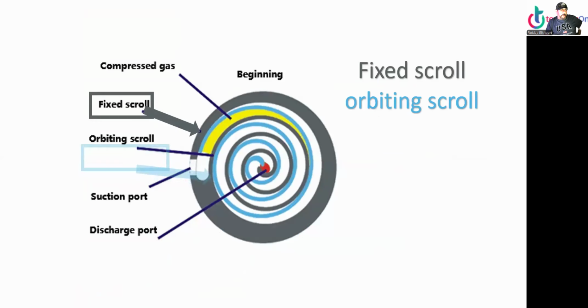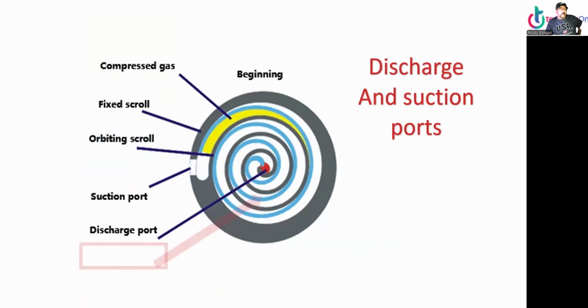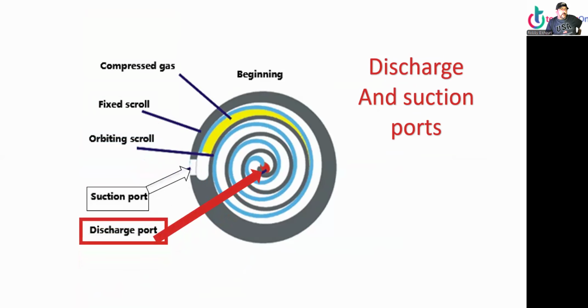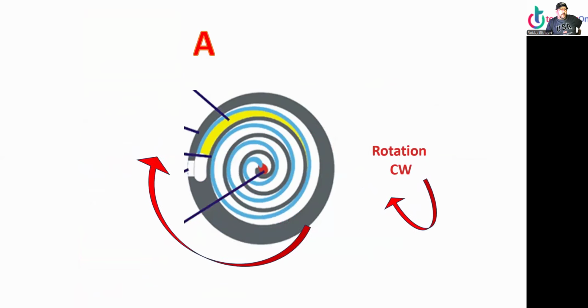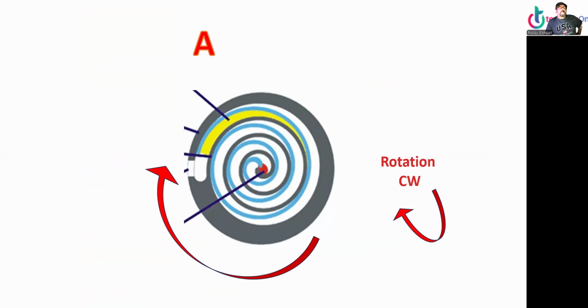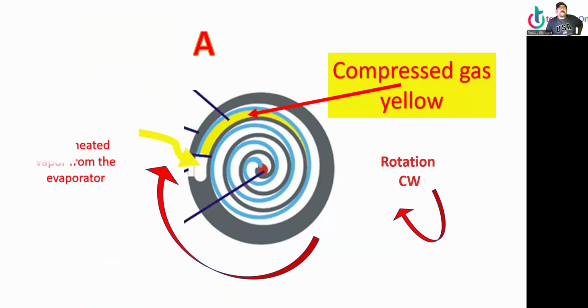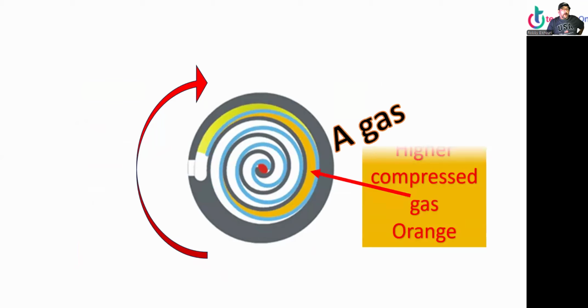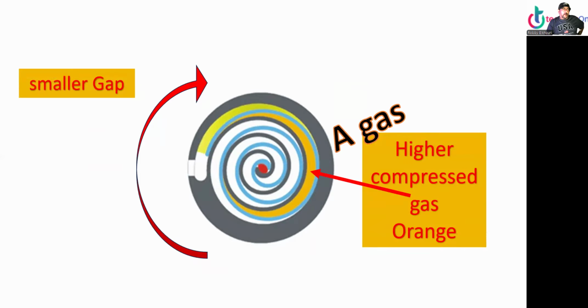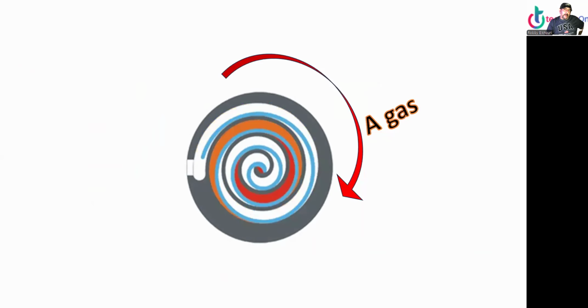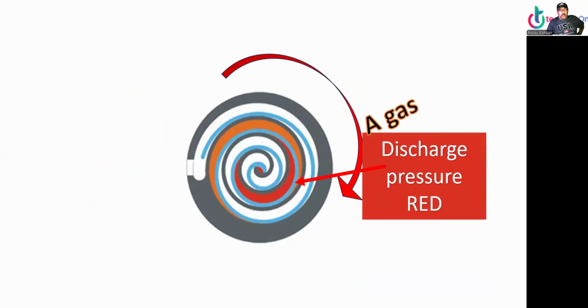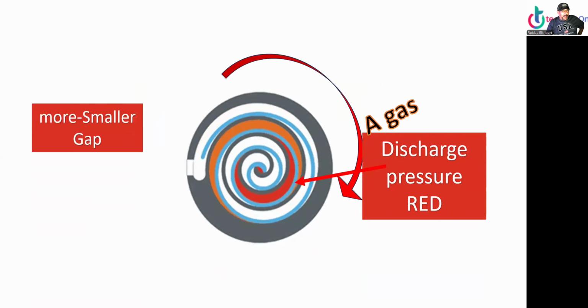So we have the fixed and orbiting scroll, discharge port, and suction port. Rotation clockwise. Must be Canadian, huh? All righty. So compressed gas in yellow. Superheated vapor from the evaporator comes in. We have a big gap, clockwise. We have higher compression, orange, smaller gap. The other one is the B gas, a different gas coming in. Now the A gas, discharge pressure is red, an even smaller gap.